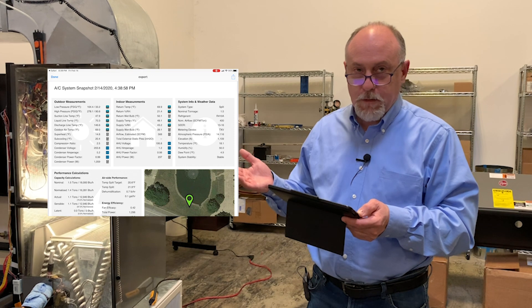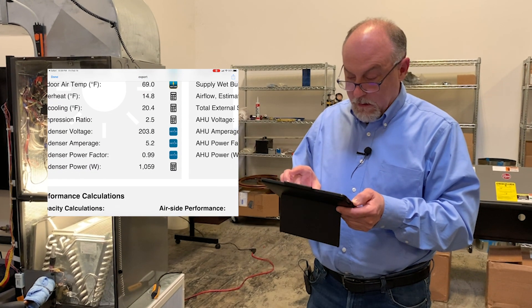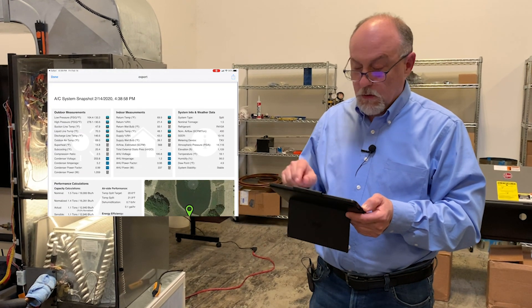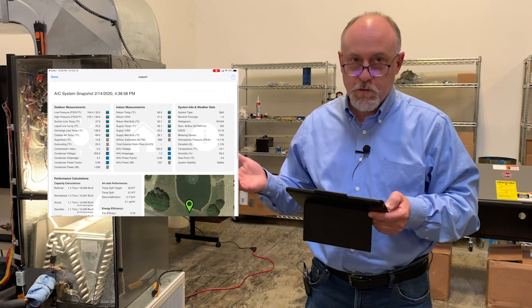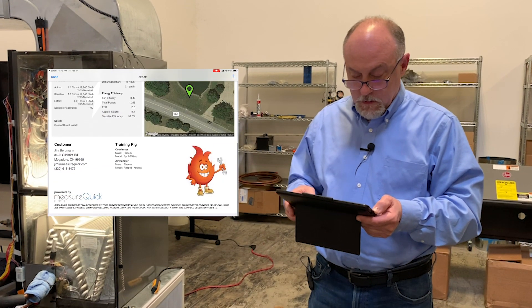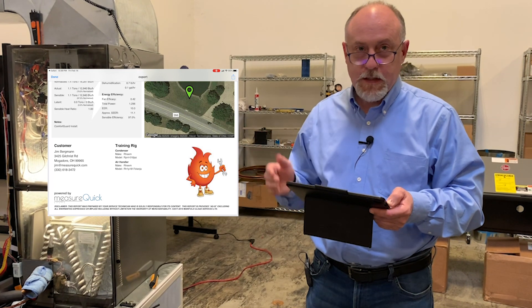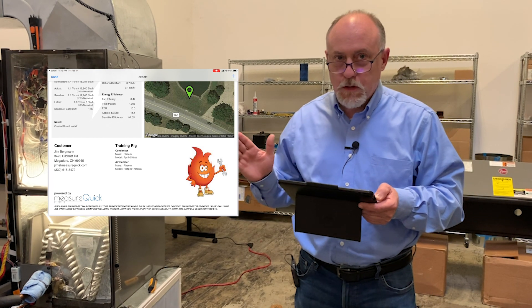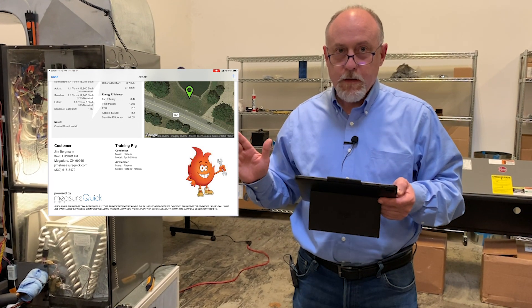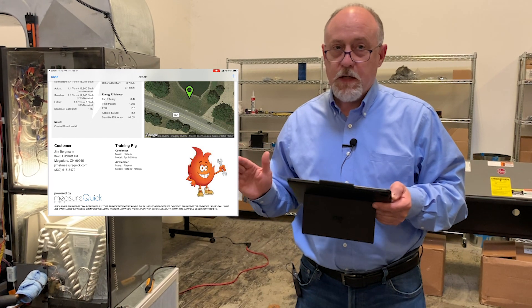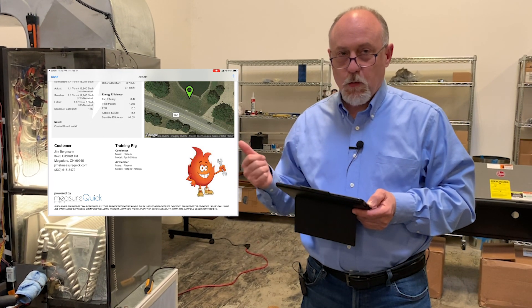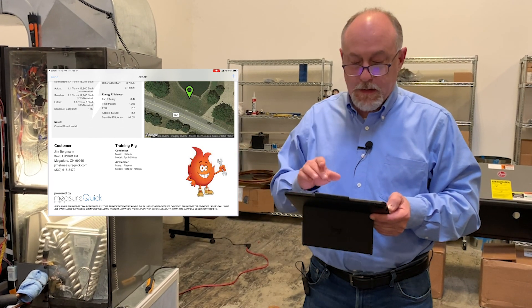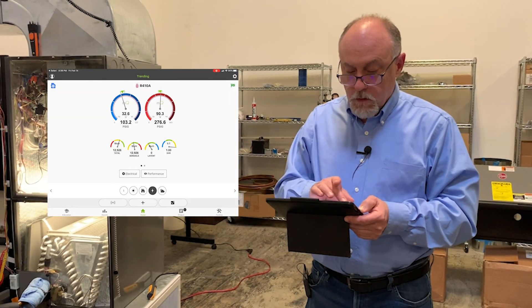I have some measurements coming off my FieldPiece probes, and I've got condenser voltage and amperage coming off the Sensi — same thing with the air handler. That makes it really handy because I don't have to grab a volt meter. I've got my tons of cooling, my logo, and basically everything's set to go. I can email the report out to the customer and I'm done. Doing a service call with Sensi Predict is monumentally easier — I came out here knowing what the problem is, where to start looking, and then I solved it and verified it.